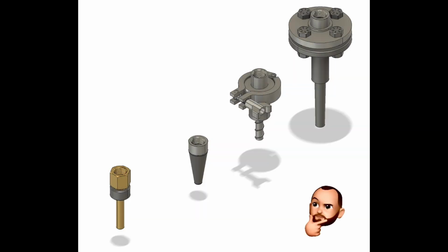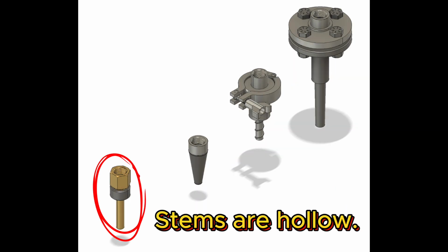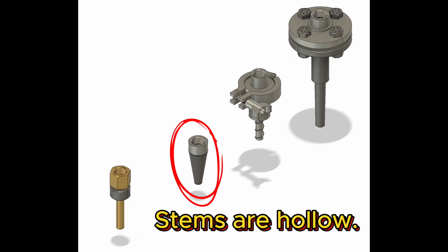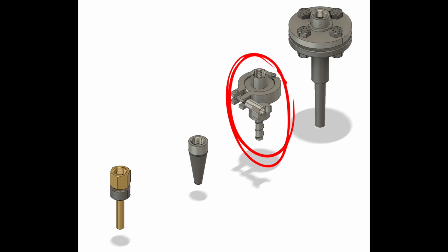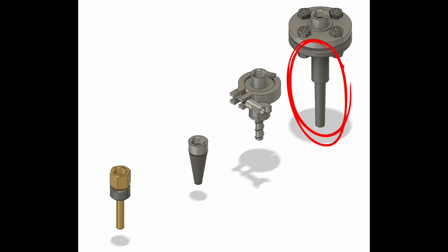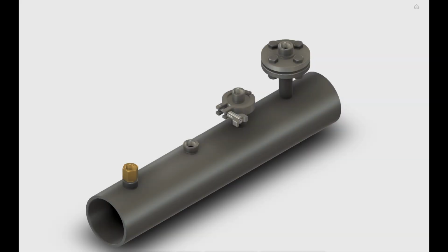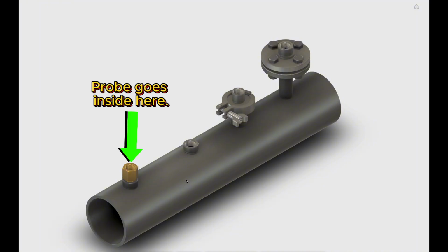So what is a thermowell? Here are 4 examples. This one has a straight stem, this one has a tapered stem, this one has a twisted or helical stem, and this one has a step stem. Basically the stem is what protrudes down inside your process piping, and then your temperature probe sits down inside that thermowell.